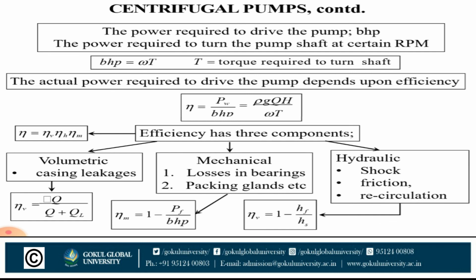Efficiency equals P upon WT, that is, rho g Q H upon WT. Efficiency has three components: volumetric, from casing leakage, mechanical, and hydraulic. Mechanical losses are in bearings and packing glands, etc., and hydraulic losses are shock, friction and recirculation.